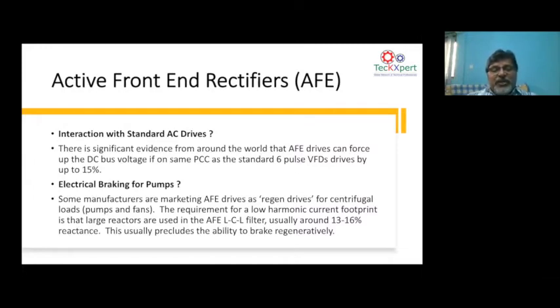But one good point I should say about active front-end drives is it can also be a regen drive, that we can regenerate. Active front-end drives can send back the extra energy that is available in a rotating motor back to the system. Sometimes, active front-end drives can also be used as a regeneration drive. For the energy efficiency concept, active front-end drives give some energy advantage. So you have to look at the trade-off between all these concepts.